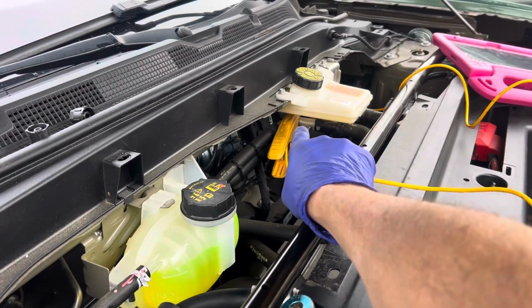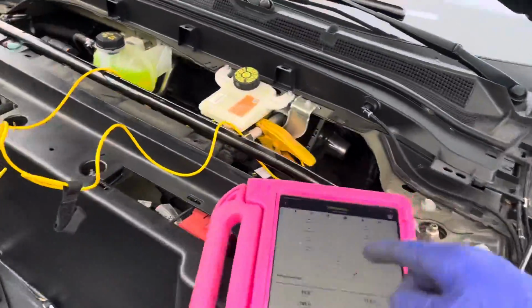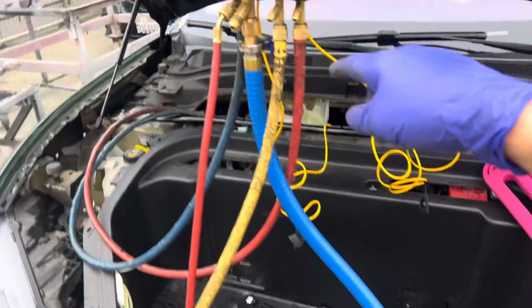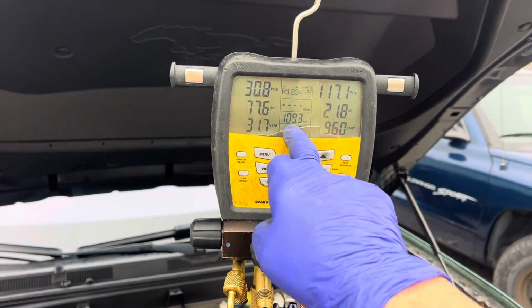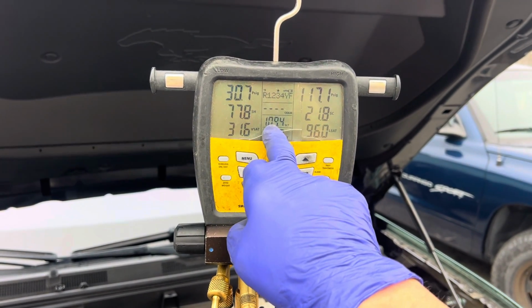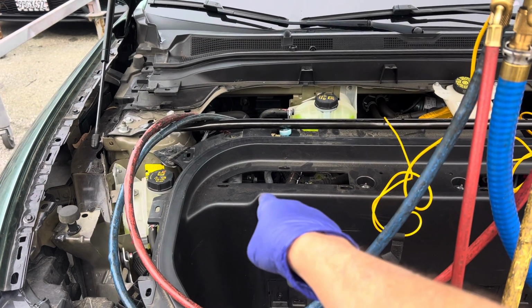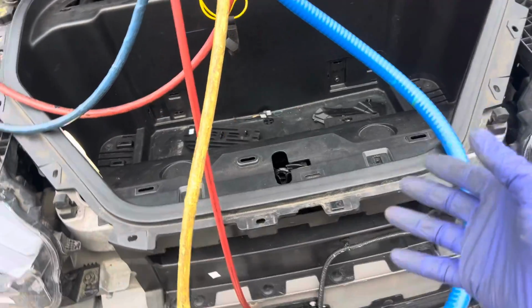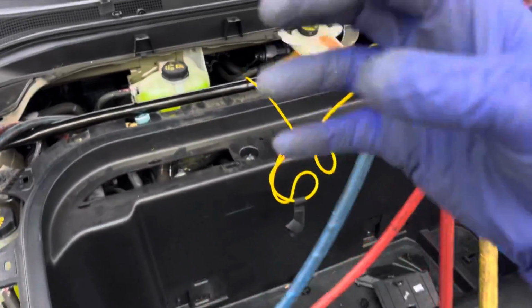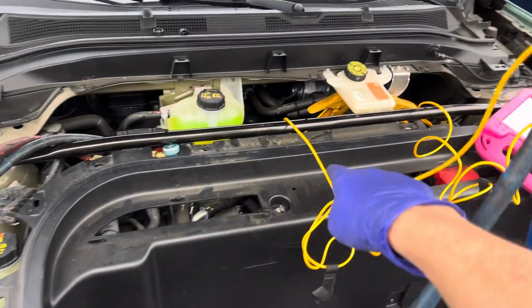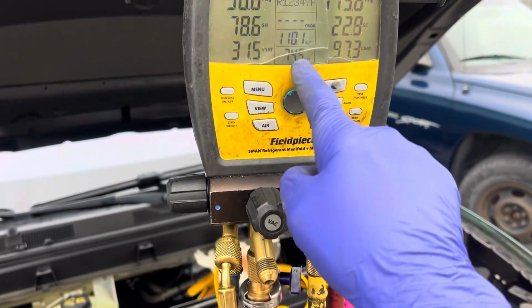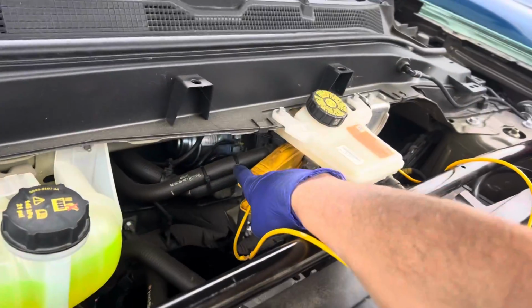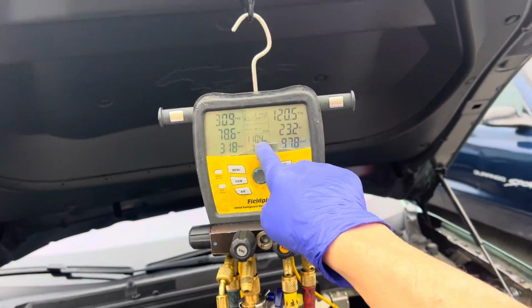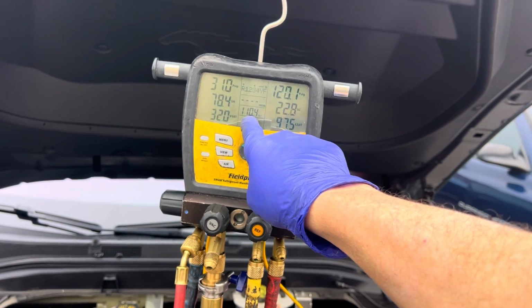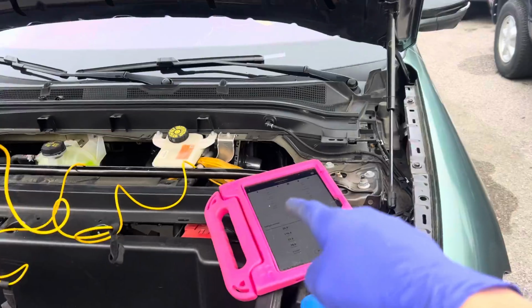Now you see my temperature probe right there on that metal line, and I'm on the metal line right here going into a heater core, and you see 109 degrees and 74 degrees. So this is my heated water that's coming from the AC compressor from the hot discharge, going to another plate heat exchanger somewhere here where we can't see right now. It's heating up the glycol, then an electric pump is pumping it over to, it's on my suction line. So this one right here, this is the source. The source water is right there at 110 degrees, and it gives off its heat into the cabin, and it's coming back at 74 degrees right here. So that's the heat loop right there.